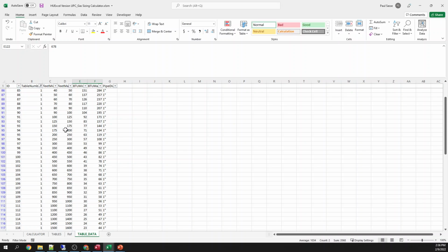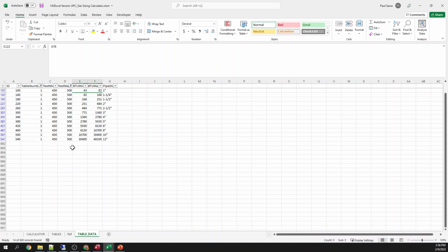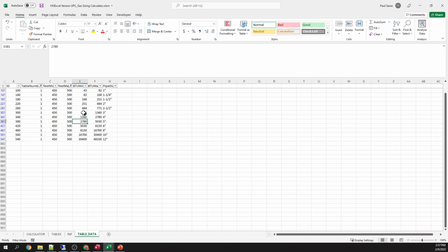Okay, let's do this. It gets a little hard for humans. See, the humans don't think this way. Computers love it. Okay, so here's all the ones that are 500 feet. Now we can figure out our BTUs. 1070. So here we go. 1070 is greater than 771, less than or equal to 1360. My length is greater than 450, less than or equal to 500. I need a 3-inch pipe.